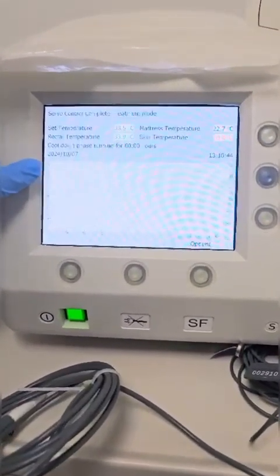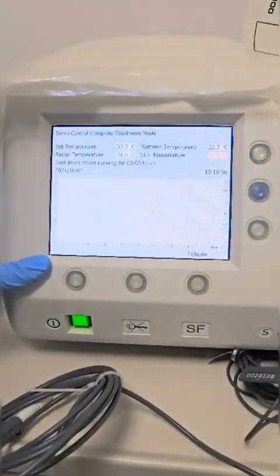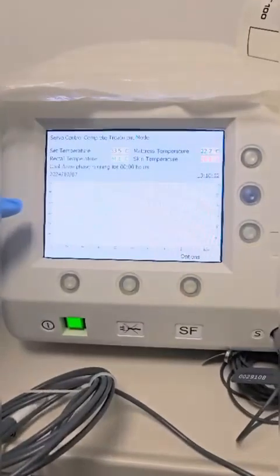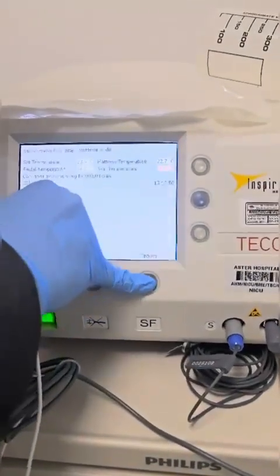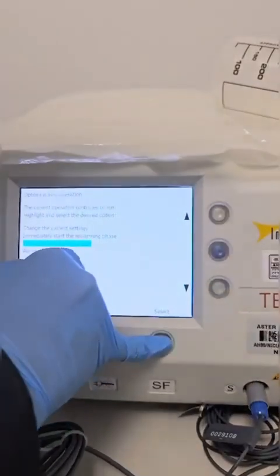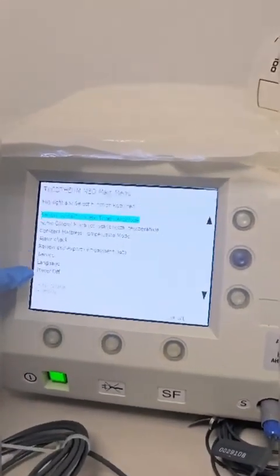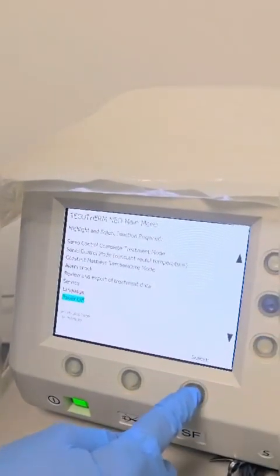In the treatment mode, you will see the temperature on the Y axis and the treatment hours on the X axis — a trend will be shown as time passes. Once you want to stop the treatment, you can go to option again, select end treatment and save data. Then you can switch off by going to power off. In this way you are operating the TECOTHERM NEO.